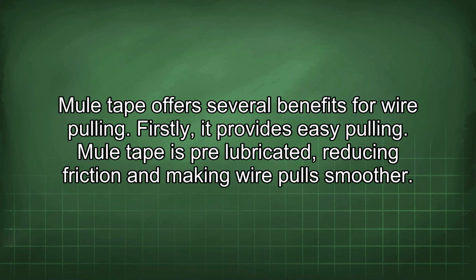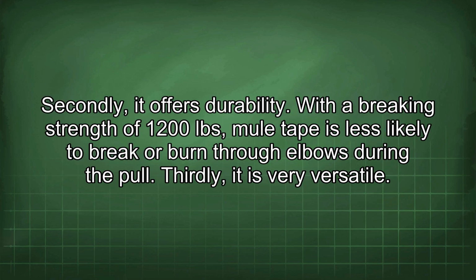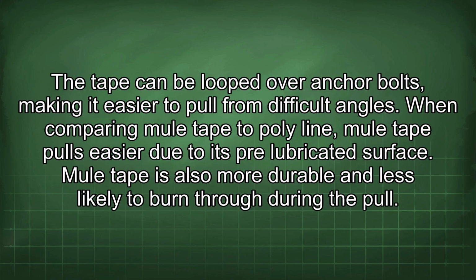Mule tape offers several benefits for wire pulling. Firstly, it provides easy pulling. Mule tape is pre-lubricated, reducing friction and making wire pulls smoother. Secondly, it offers durability. With a breaking strength of 1200 pounds, Mule tape is less likely to break or burn through elbows during the pull. Thirdly, it is very versatile. The tape can be looped over anchor bolts, making it easier to pull from difficult angles.